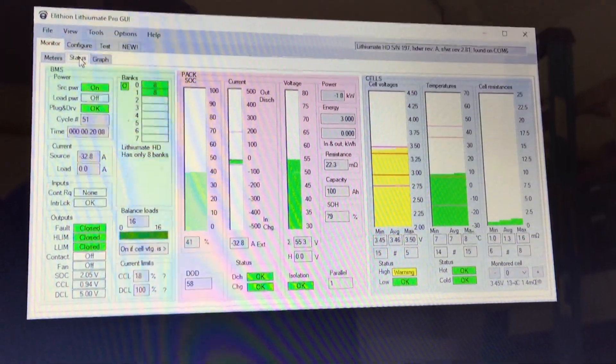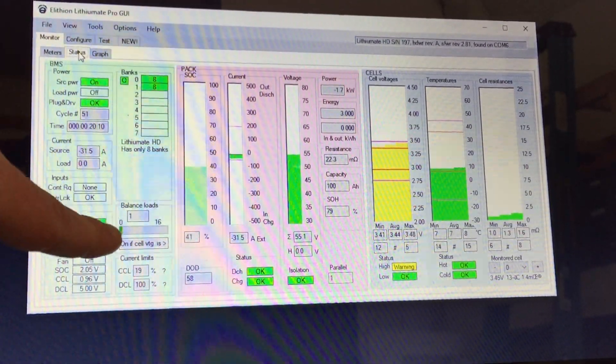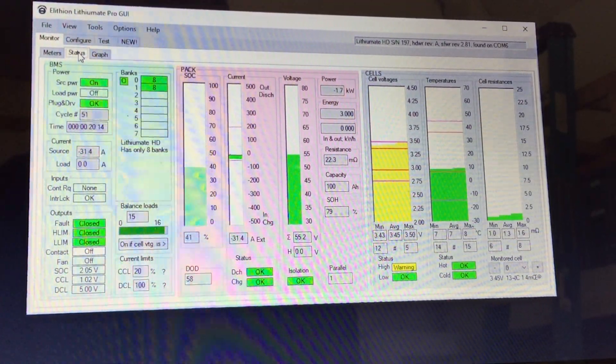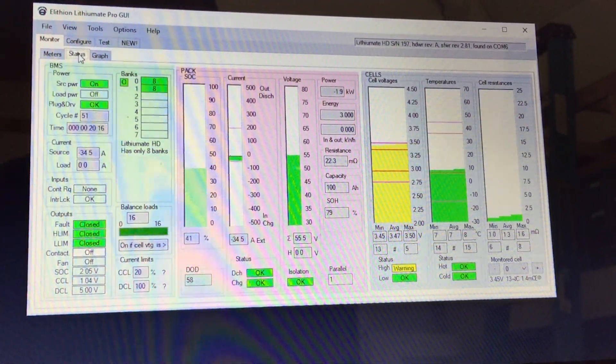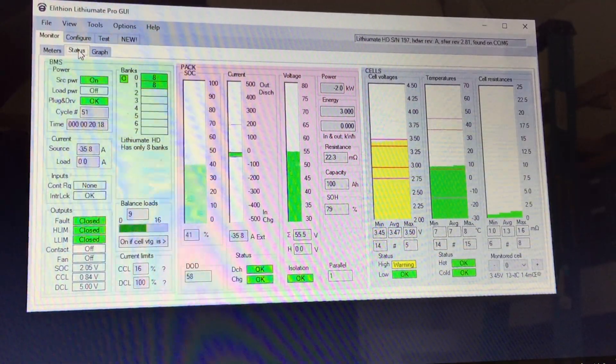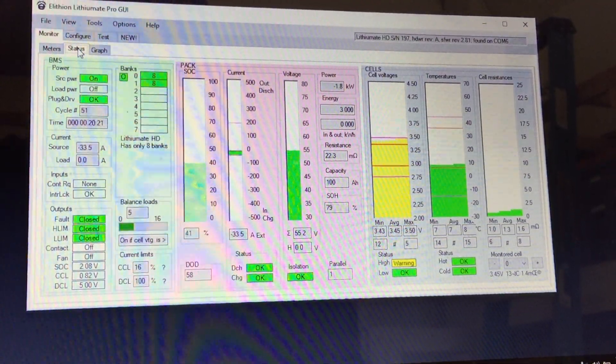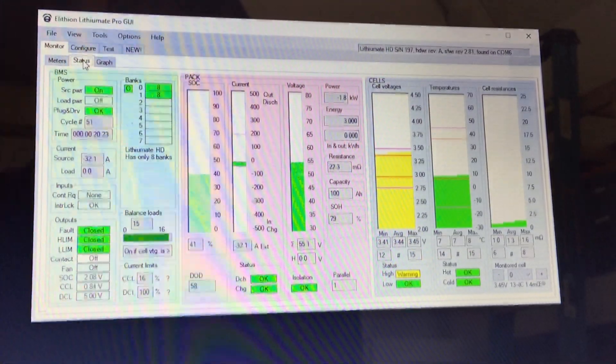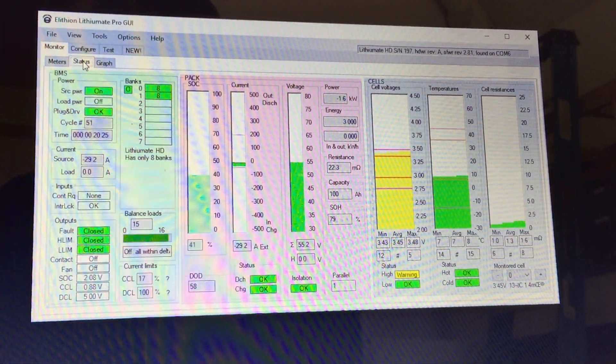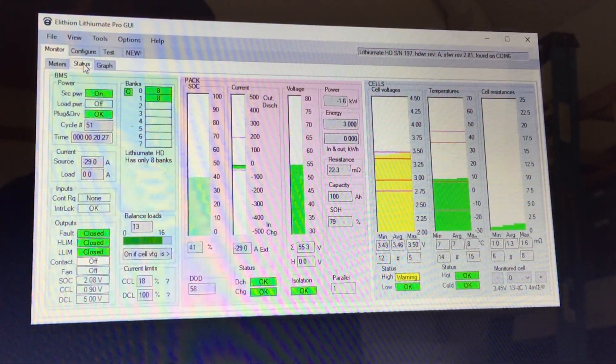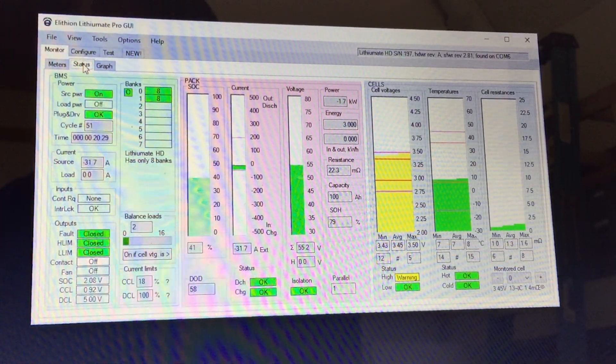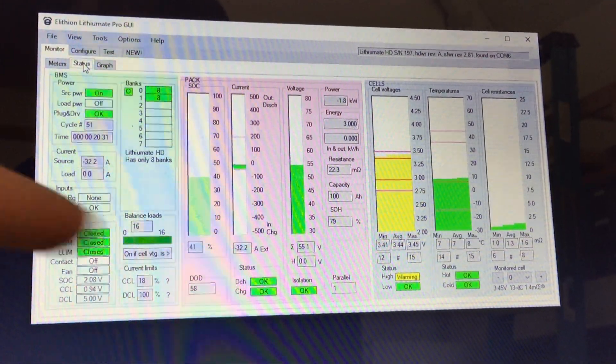What we're seeing is the battery is balancing any cell above 3.4 volts with two-hundredths of a volt difference. We're seeing this battery operate exactly as designed, with charge regulation and derating occurring as the battery is approaching full.